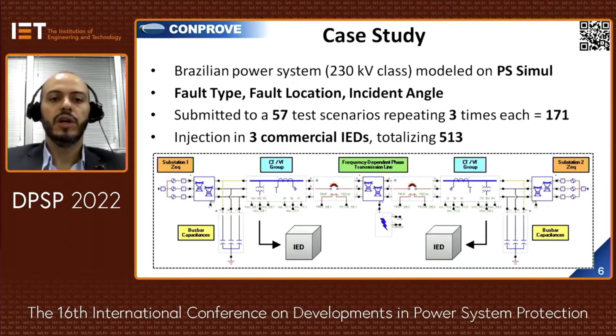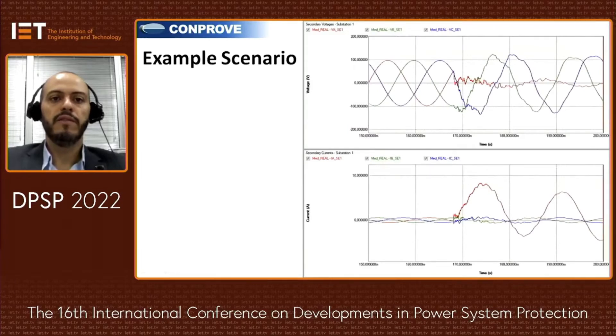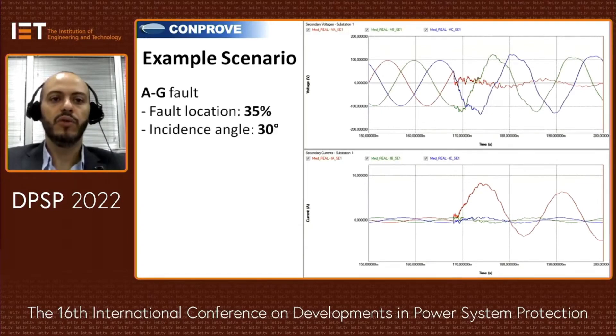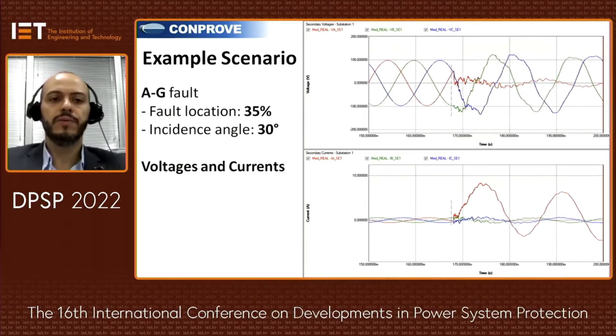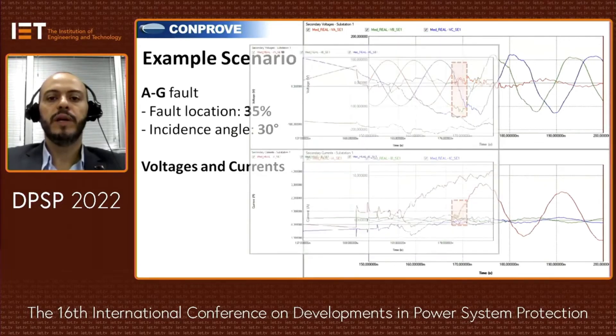Here on screen is the modeled system. In the middle we have the transmission line with a frequency-dependent model, circuit breakers on each side, and CTs and VTs on each side. Bus bar capacitance was also modeled — this is really important for TW simulation — along with the equivalent of the rest of the circuit. Here is a detailed scenario of one injected test: an AG ground fault in substation 1 at 35% location and an incident angle of 30 degrees. Above you can see the voltage and below the current signal; with a zoom you can see the waveform and the high-frequency content in detail.